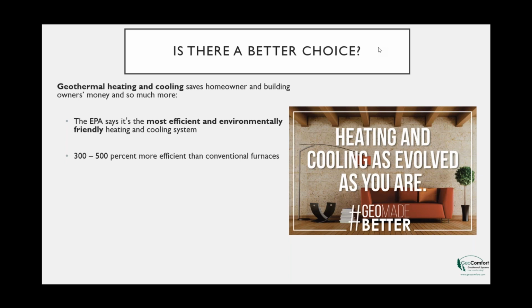Like I mentioned, we're not burning a fossil fuel. So anything that burns a fossil fuel cannot achieve more than 100%, because when you burn something, there's always something left over in the form of a flue gas that goes out the chimney or out the flue. With an electric-driven heat pump, we can achieve more than 100%, because even though we're using electricity, we're multiplying those kilowatts by moving energy instead of creating energy. So we're putting that ground loop in the earth, and we're taking that energy and moving it from the ground into the home by using the heat pump technology. And so that's how we can get higher than 100%. And as you see here, 300 to 500%. And with this new all-in-one variable speed product, we'll show you that we can actually achieve up to 600% plus efficiency with this product. COP and efficiency are a direct correlation. So we'll show you that here in just a bit.